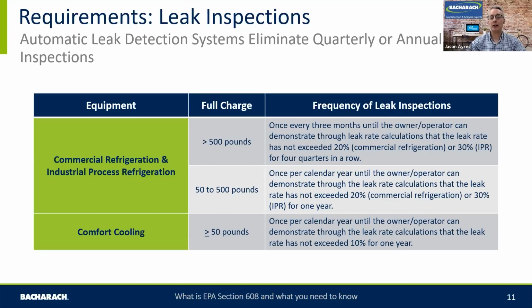If you use refrigerant, leak inspections are a requirement. You must document that you've carried out those leak inspections and have those available. One of the benefits of having an automatic leak detection system on those sites is that it eliminates the need for those physical leak inspections. So if you have a leak detection system that's covering part or whole or the entire refrigeration system, you don't physically need to go to site to do those inspections. That automatic leak detection system that's looking for the leaks mitigates that requirement. But again, you need to capture it, you need to be aware of it, and you need to record it.